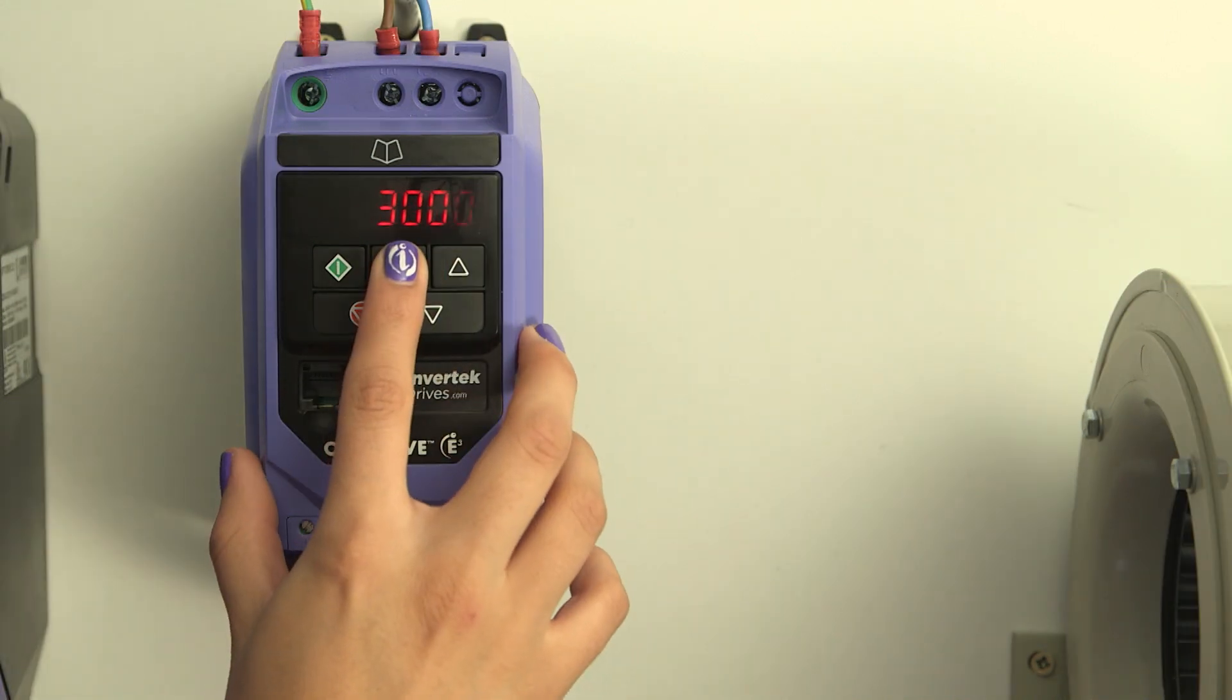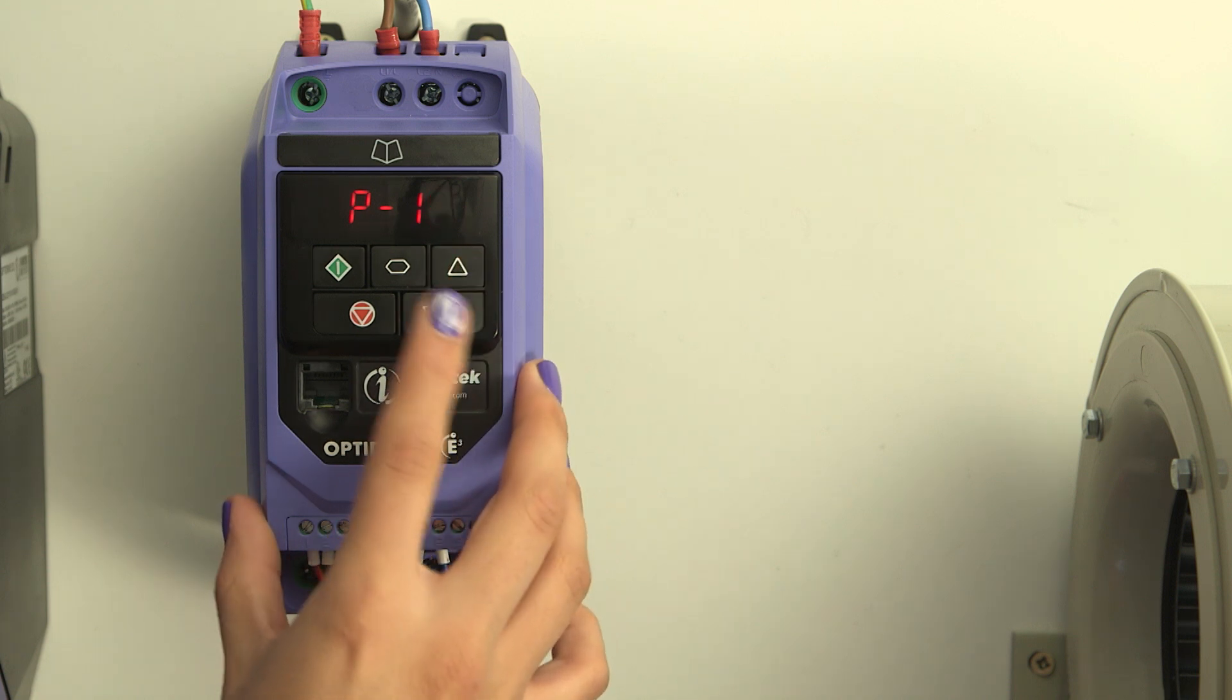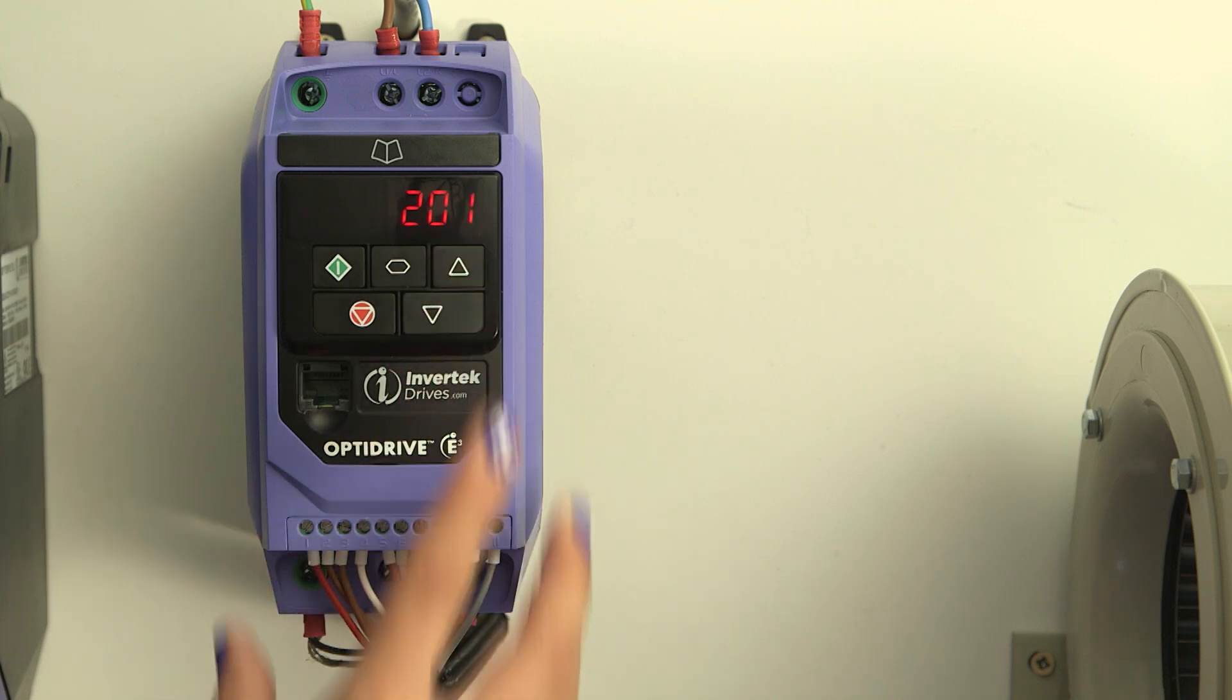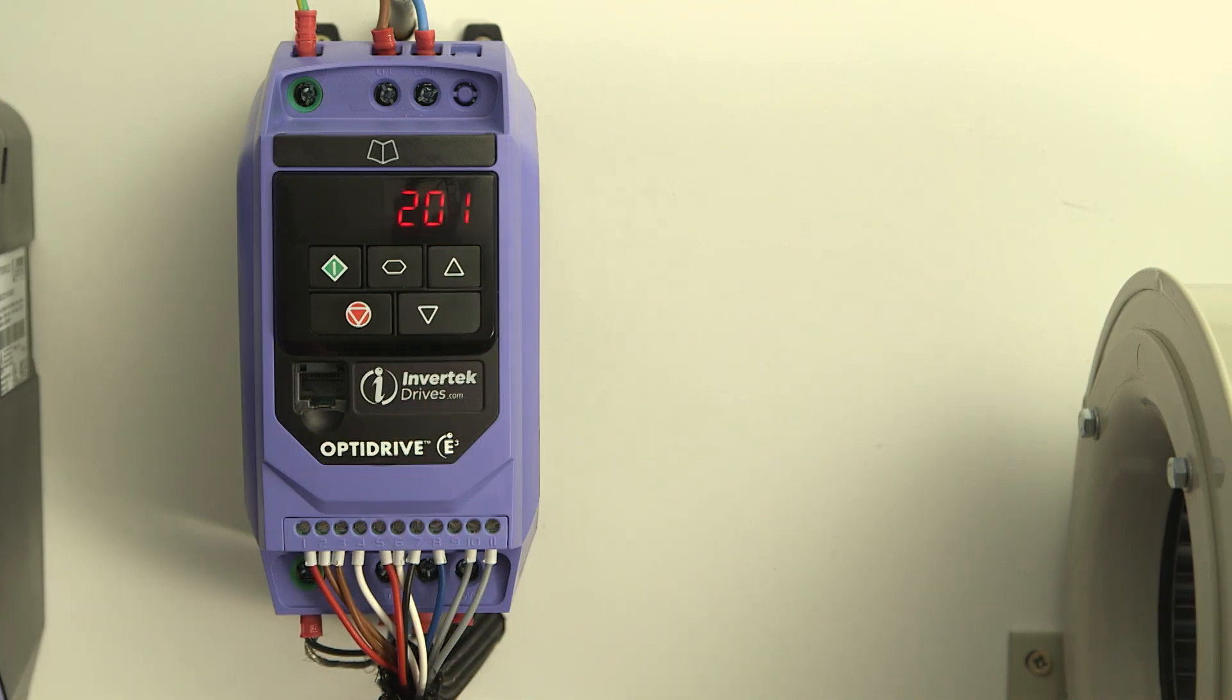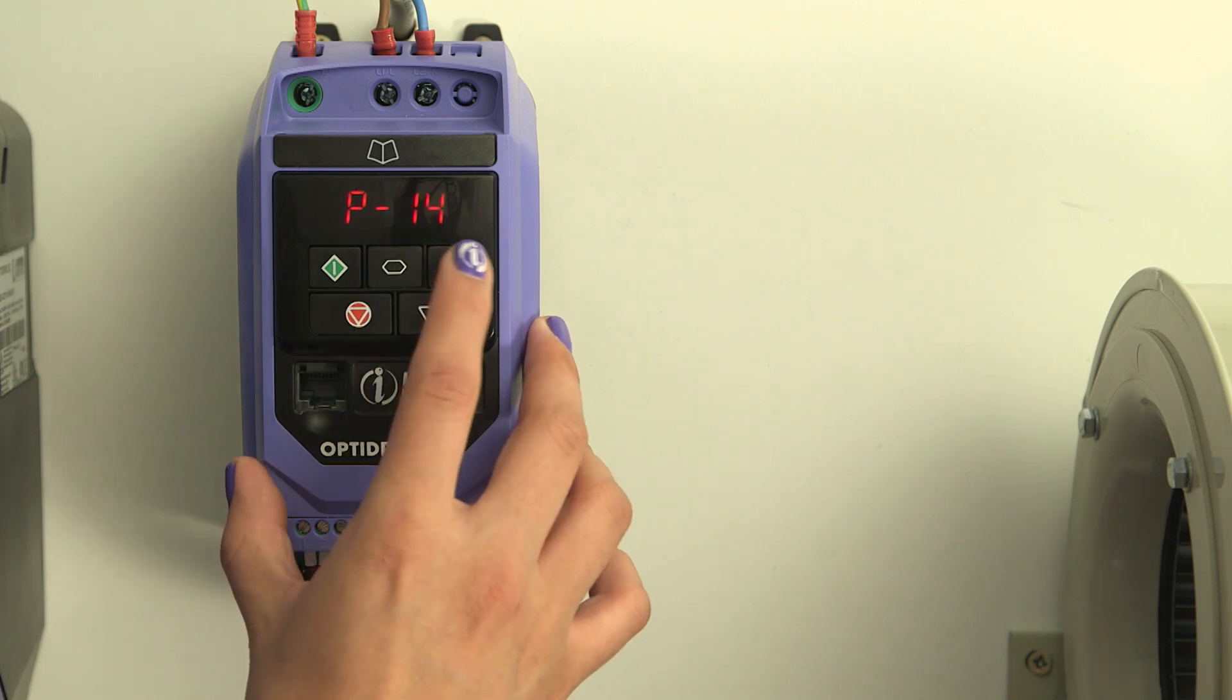To access all the other parameters, we will need to set parameter 14 to 201 to access the extended parameter set. It is recommended to use a switching frequency of 16 kHz for these motors, so we'll just check that in parameter 17.